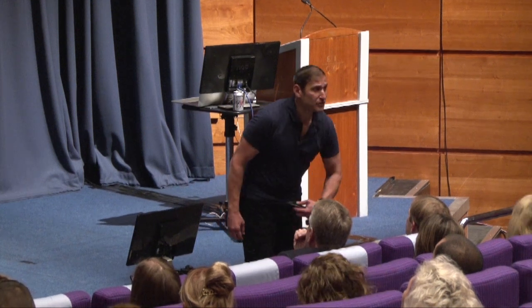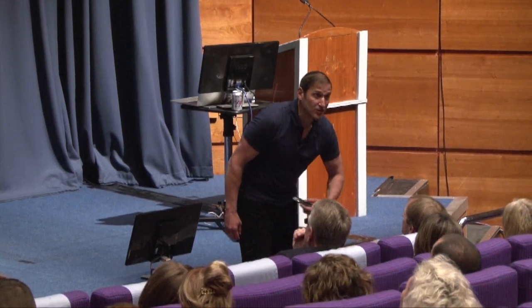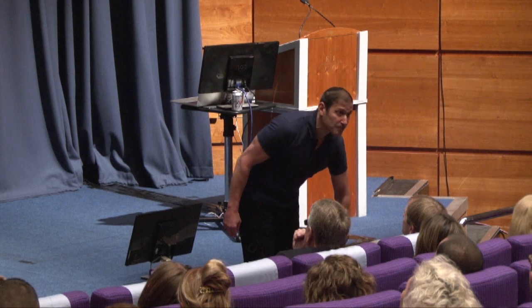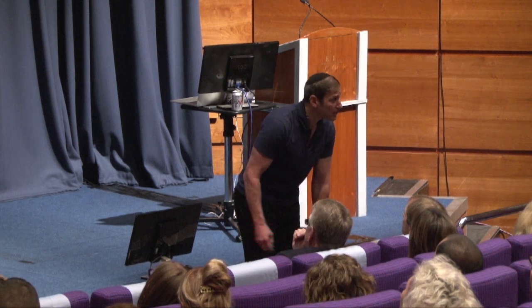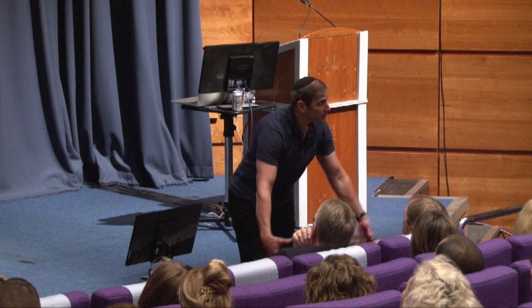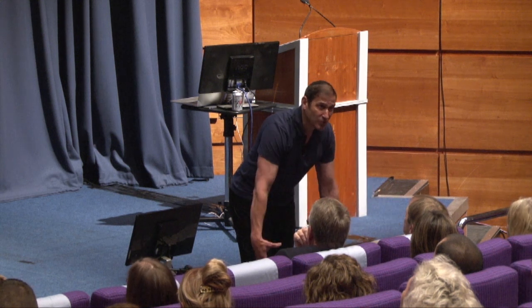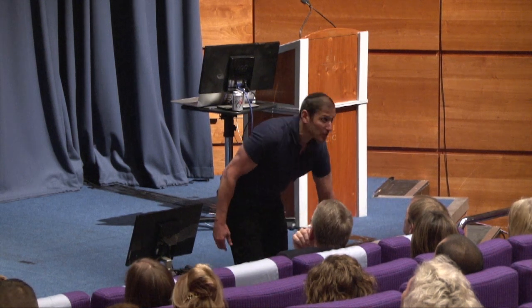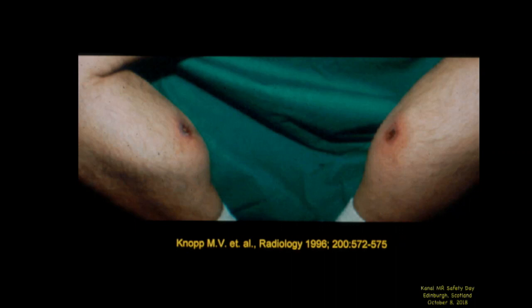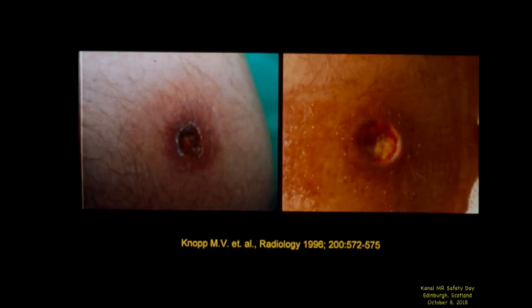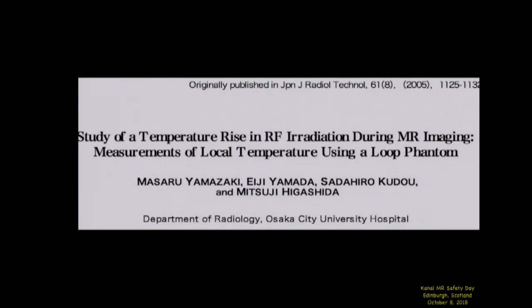He had massively hypertrophied calves. And can you see this huge loop right here? His medial thighs were not touching. His calves were touching. RF coil, the body irradiating right over here. Probably the largest loop a human can form other than trying to touch your toes in the magnet. And with a very large loop, he developed kissing third-degree burns. This is months later. These third-degree burns were present on this patient.